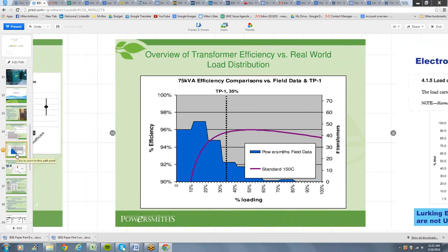And this has several implications. What those implications are, overlaid with a typical transformer efficiency curve, is you can see I've got the loading in blue stacked to the left-hand side, in the 10, 15, 20% range. On top of that, you see the purple line, being the efficiency of a typical transformer, and it noses off really rapidly as you get down to lower and lower loading. So there's a disconnect between the nameplate efficiency and the target efficiency required by law, which is set at 35%, and the actual environment the transformer is operating in, where much lower load means much lower efficiency. So there's really an illusion of efficiency in transformer practice because of that light loading reality.